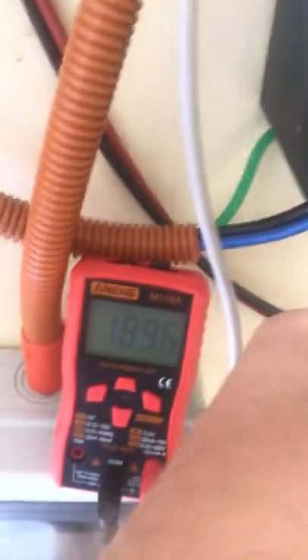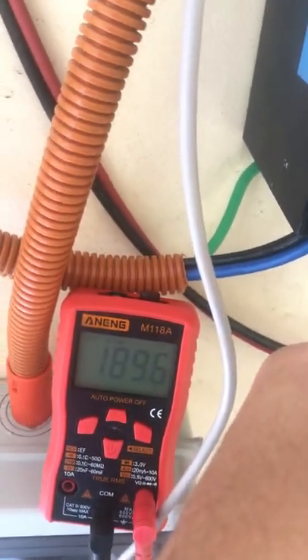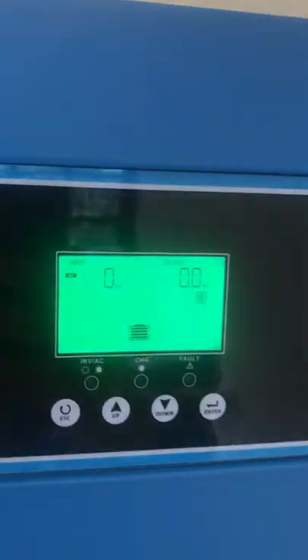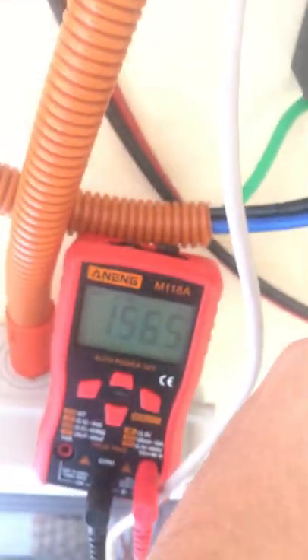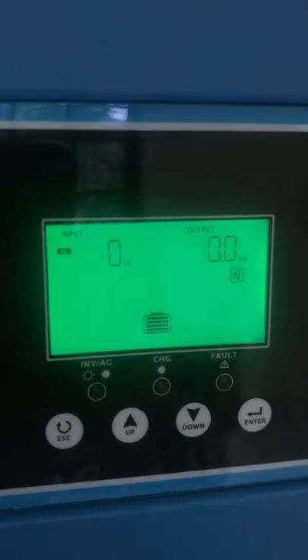So here is this problem again. The unit is on, the battery is connected, the line is connected, there are 189 volts in here, and the unit shows 0 volts. If I switch to frequency, it shows 0 hertz. So the line is definitely connected here, but the unit does not see it.